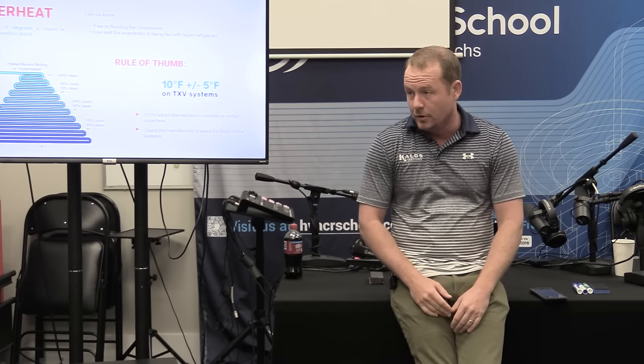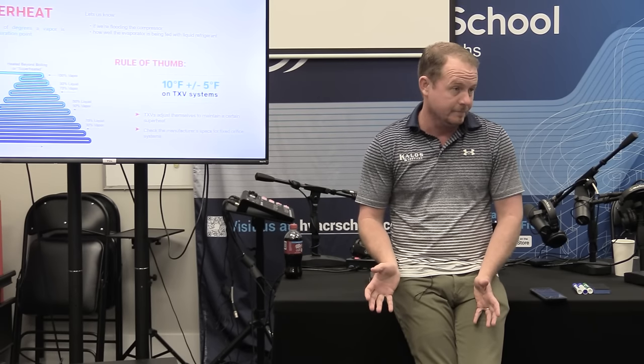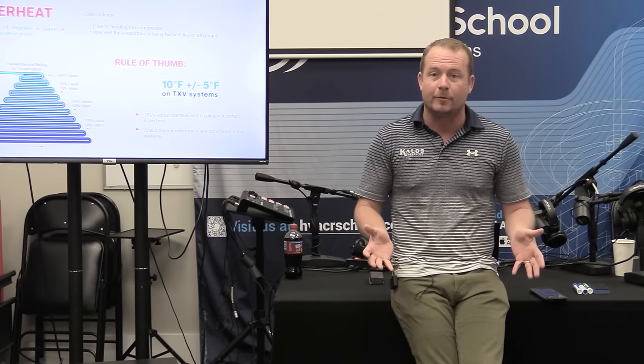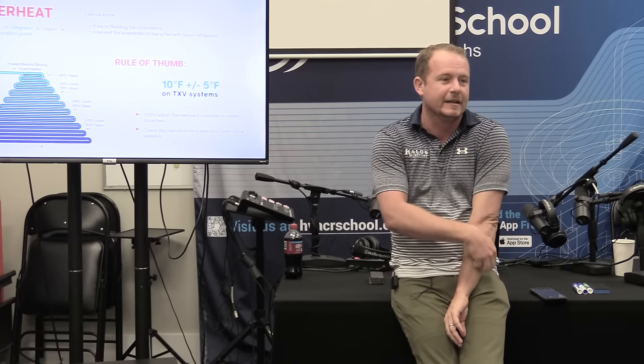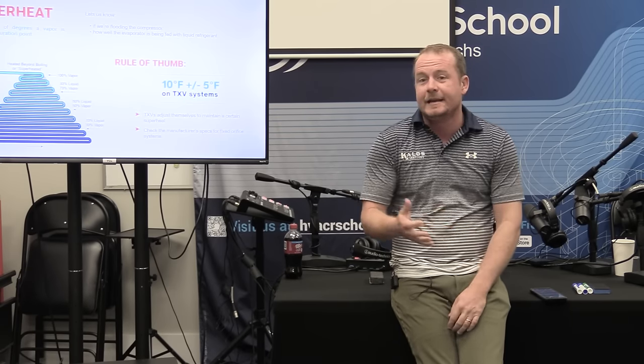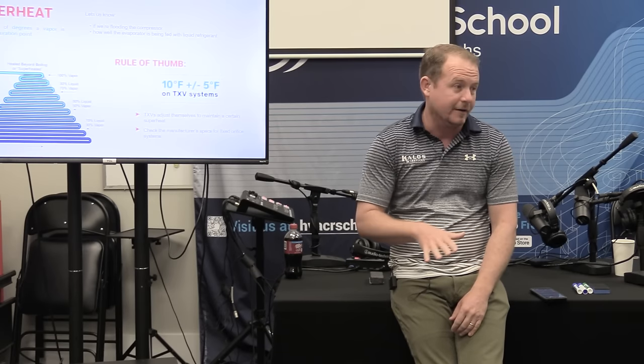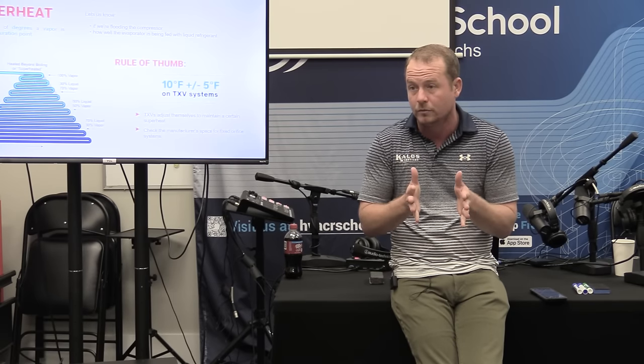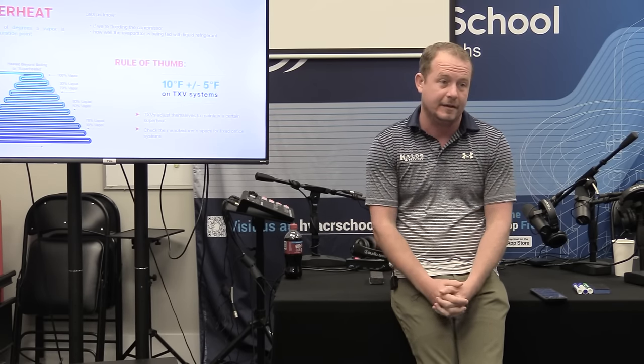That's why when you have a system running in dehumidify mode, it's not going to run as efficiently — you're not going to get as many BTUs per watt of input, meaning you'll spend more money to cool your house. But when you have a nice cold evaporator coil, you're not going to have mold issues. In Florida we need cold evaporator coils, or at least the ability to have a cold evaporator coil, or we're not going to dehumidify the way we need to. We need to know the evaporator temperature — in this case, we said it was 45 degrees.